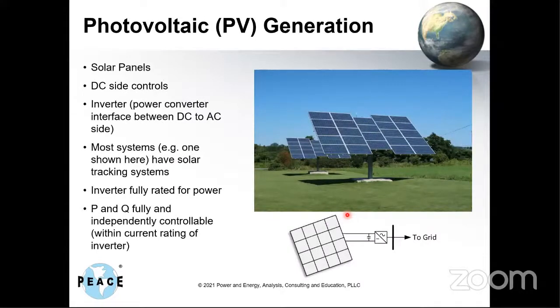Then we have photovoltaics, and I think this is the main thing that goes into your system in Chile. Correct me if I'm wrong. You have a lot of good sunlight. So this is just basically solar panels connected by a converter. So you only have one inverter now going from DC to AC. You may have a DC to DC converter here as well, just to control and regulate the DC bus. But basically, again, you have this converter interface that is fully controllable, and you can control real and reactive power independent of each other within the current rating of the inverter.